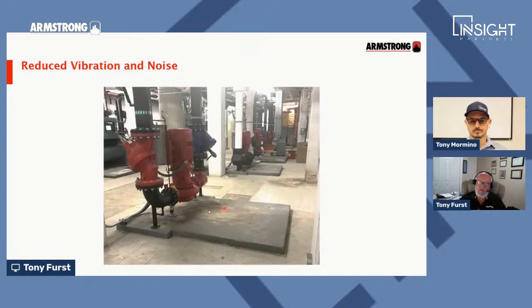Now, granted, this is an existing mechanical room, so they didn't gain leasable, rentable, or usable space for tenants, or space for classrooms or education space. But think about it from the maintenance guy's perspective - now he's got a lot more room to work on that pump. If this mechanical room were redone, those pumps could have been moved closer to the wall. You'd have gained aisleway space down the middle of the room, possibly room for another chiller. There's all kinds of things that could have been done, but because this is a retrofit, I love the visual of the difference in space between a vertical inline and a horizontal end suction or horizontal split case.